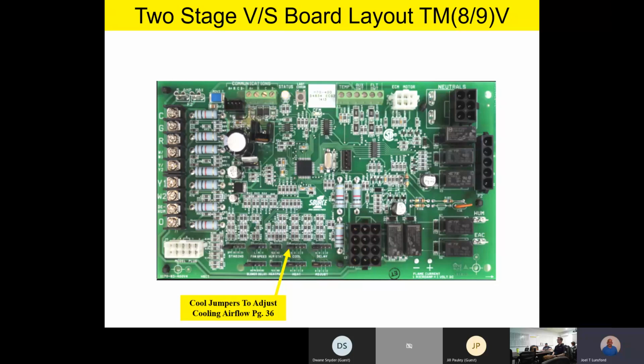Now hang on a second. What if I only have a single stage unit sitting outside? If I have a single stage unit outside, I'm going to automatically utilize the Y/Y2 terminal only on the control board. Let me say that again. If I have a single stage unit outside, you won't even use the Y1 terminal on the board. You'll go strictly to Y/Y2. So please keep that in mind with this control.